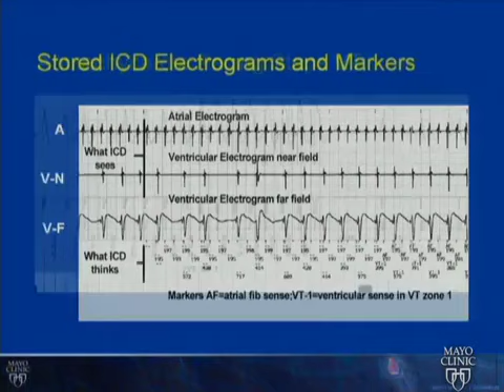Defibrillator function has usually two therapeutic functions: one is anti-tachycardia pacing, and the other is defibrillator discharges. In this recording, one sees a person in tachycardia, and the device marker channel is telling us that the cycle length of the intervals was approximately 360 milliseconds. That translates to about 160 beats per minute. That rate was programmed into the device, and the device is detecting this as ventricular tachycardia. The device was programmed to overdrive this ventricular tachycardia, usually with 8 beats as a conventional duration. This particular episode of ventricular tachycardia was treated with overdrive pacing, and the tachycardia was terminated.